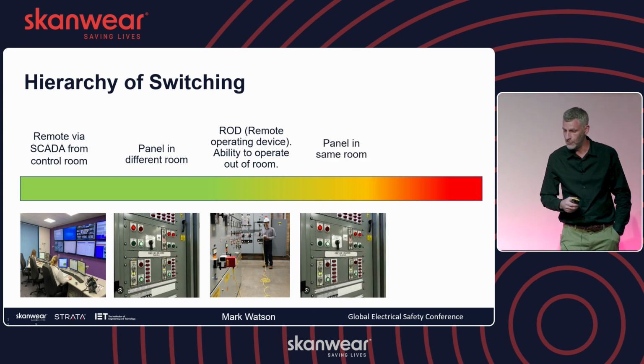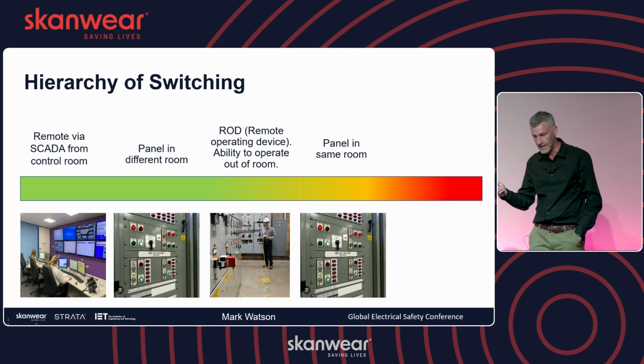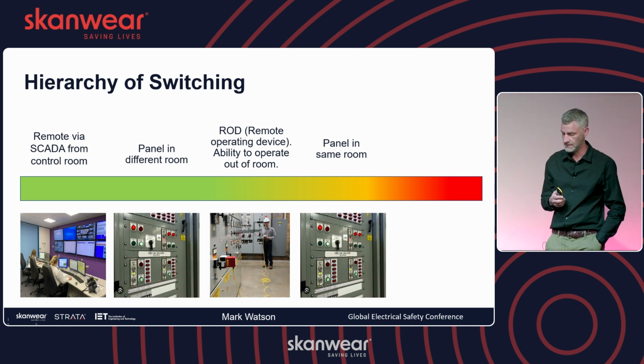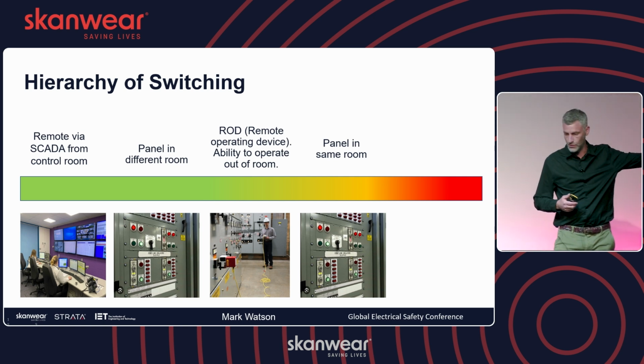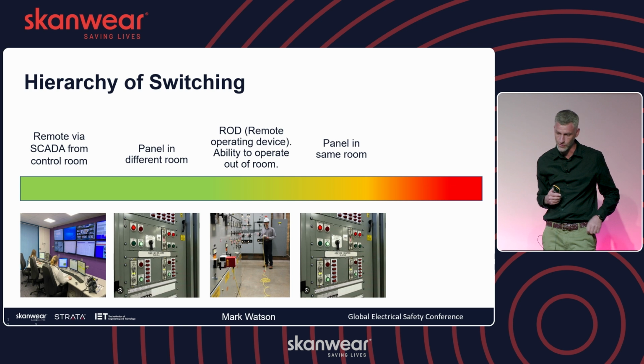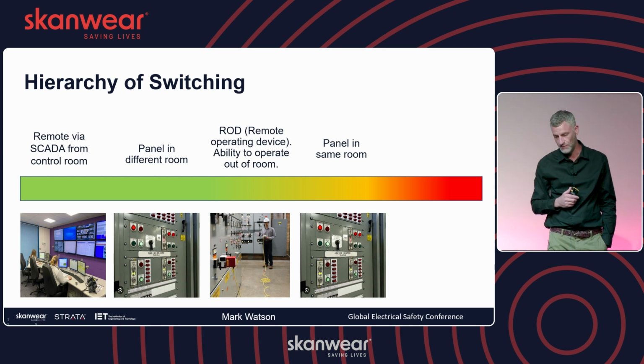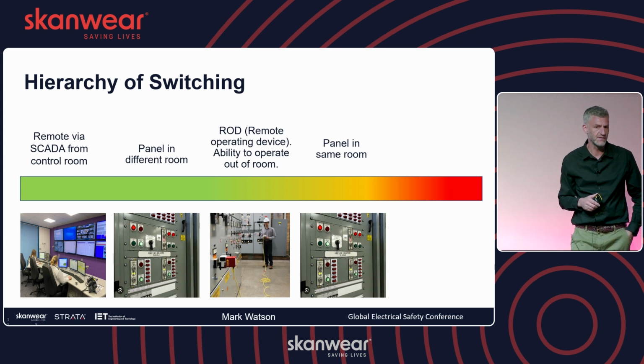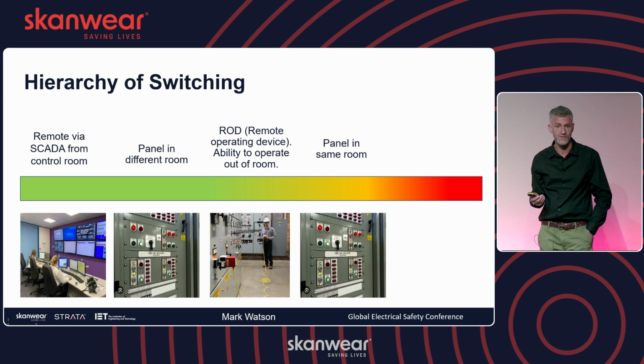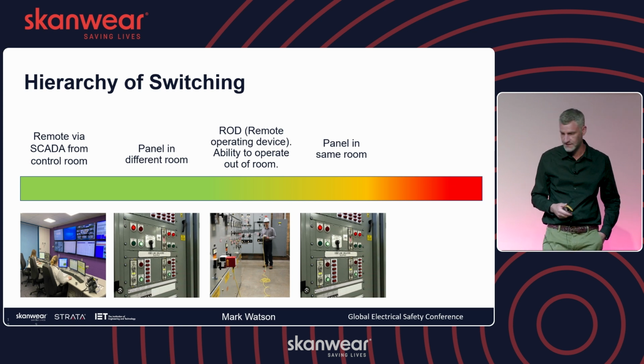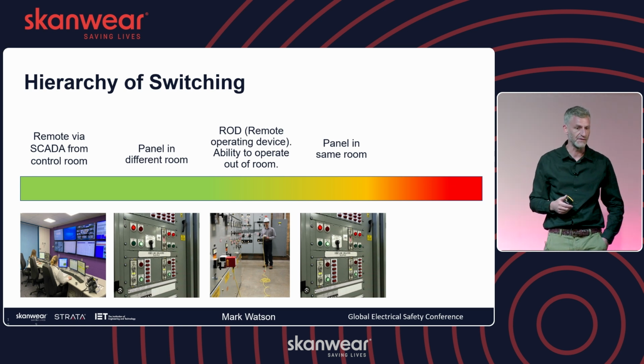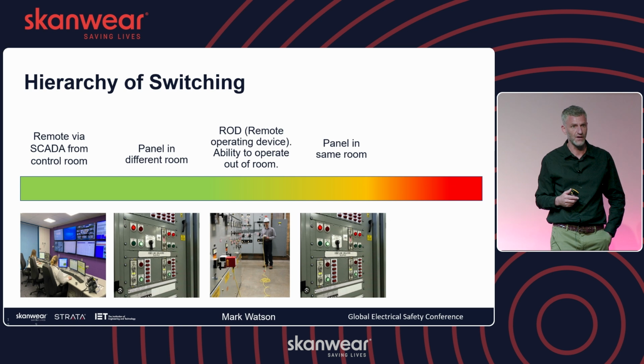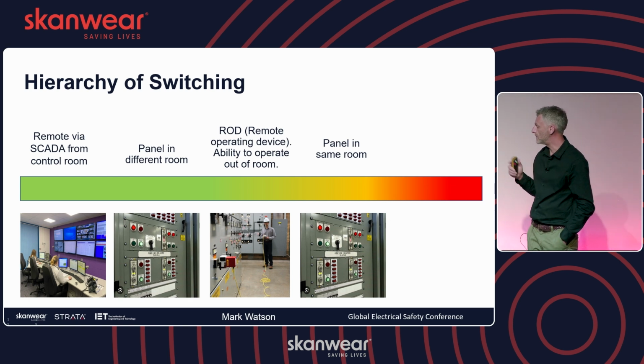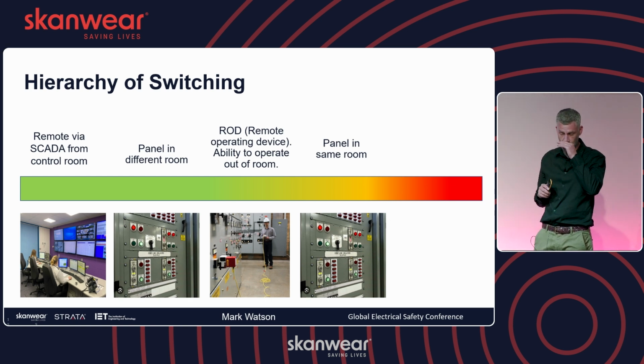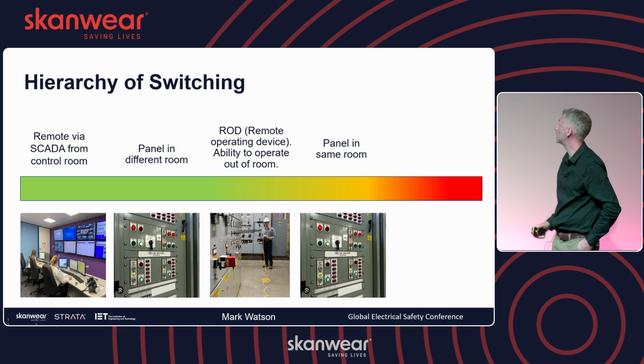Panel in the same room - we're getting closer to the risk now. If you've got switch gear in one corner and your panel in the same room, think carefully about layout during the design process. Where should we put them? Don't put it right next to the switch gear, you're not benefiting at all - put it on the other side of the room instead, so we're still keeping out of harm's way and the risk potential is lessened.